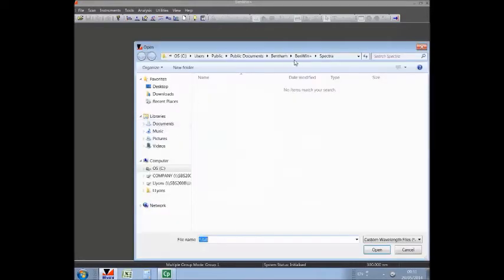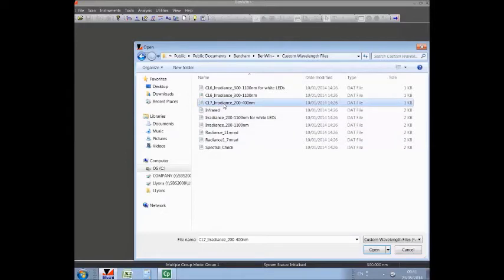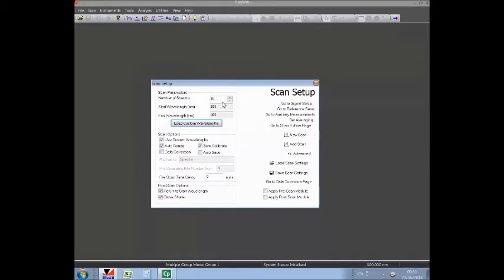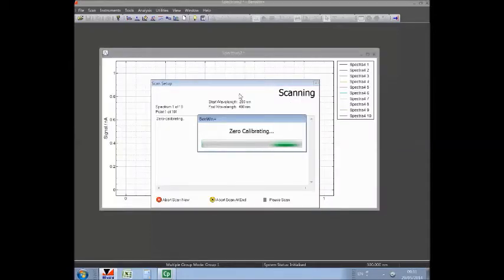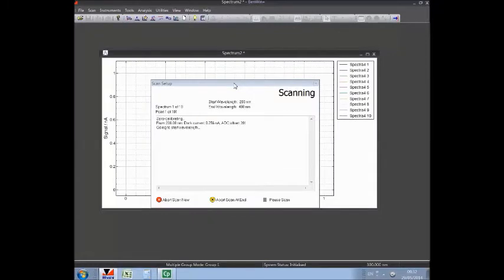A custom wavelength file is provided for this calibration, although not actually required, since the step size of 2 nanometers is applied throughout the range. And we will select another 10 spectra to allow for lamp warm-up time and ensuring that the system is stable. Now we hit new scan, and we will only see the zero calibration data of the single photomultiplier, since it is the only detector included in the spectral range of this measurement, and the 10 measurements will advance, and we will pick that up at the end of the scan.